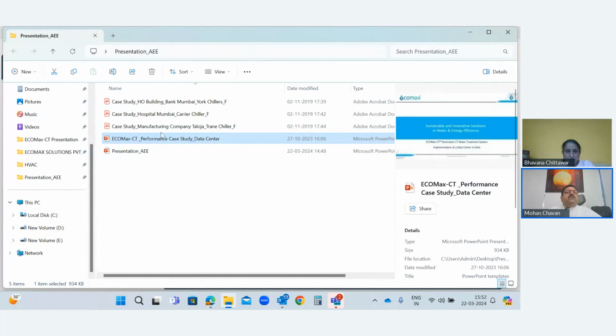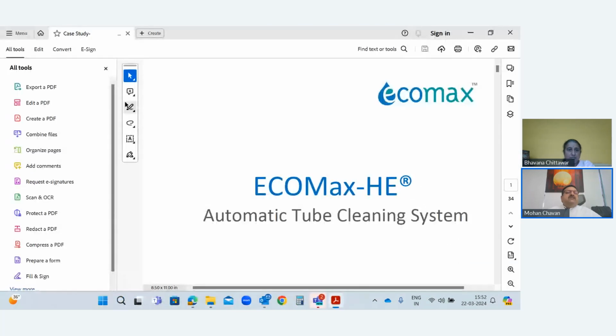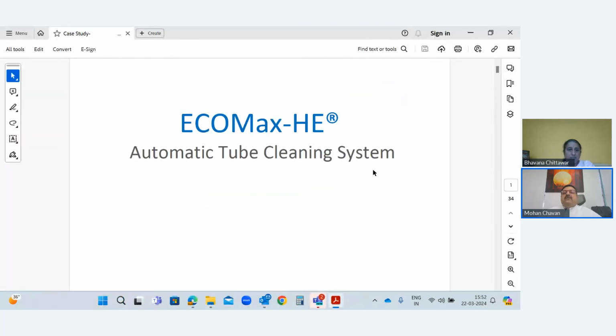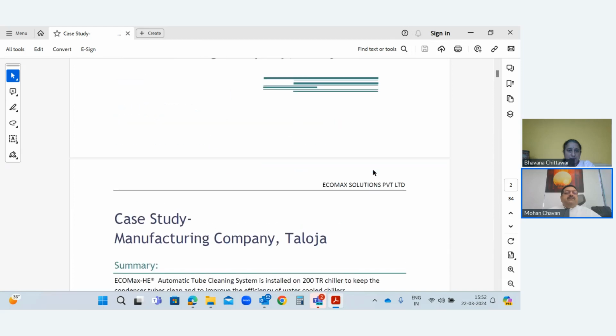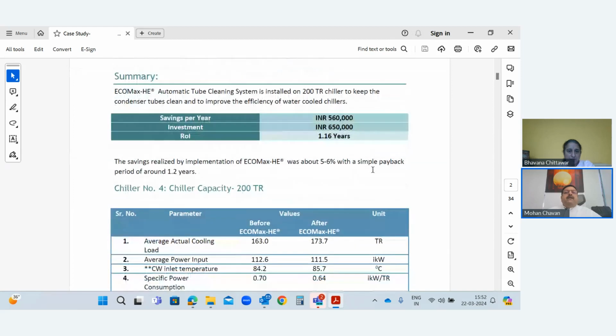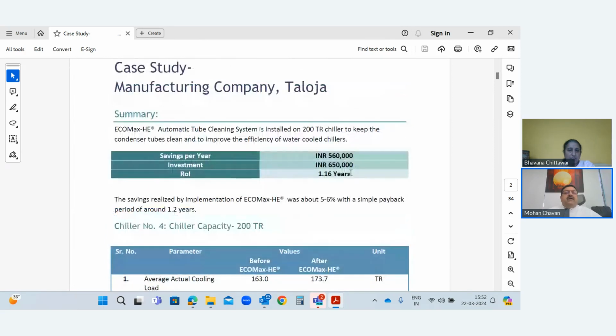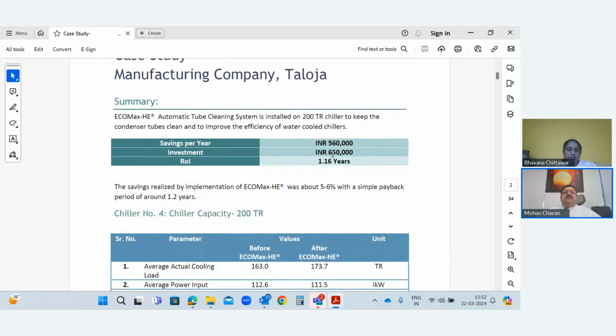We'll quickly run through one of the case studies for the chillers as well, for the automatic tube cleaning system. So this study was conducted way back, about 5-6 years back, for a 200 TR chiller, wherein investment was about 6.5 lakhs and savings per year was 5.6 lakhs. So payback of almost around 1 year in this case.